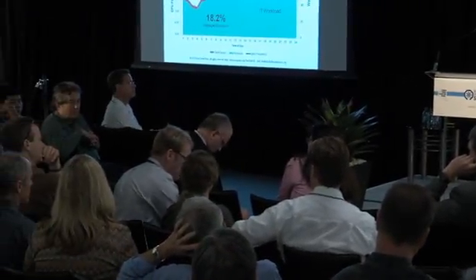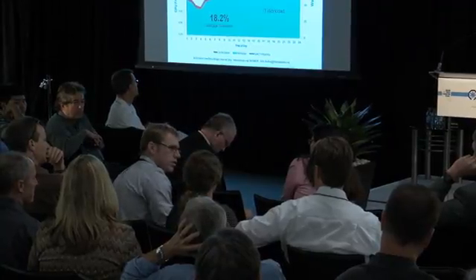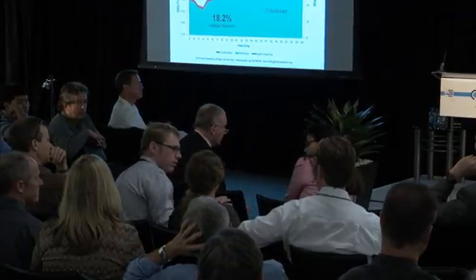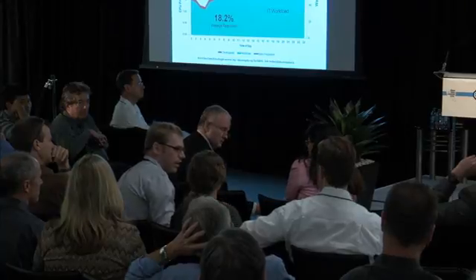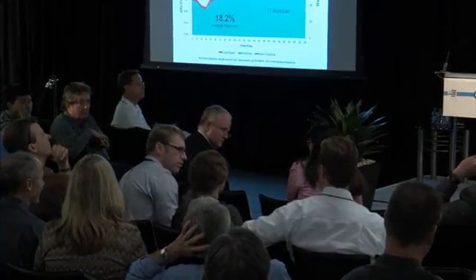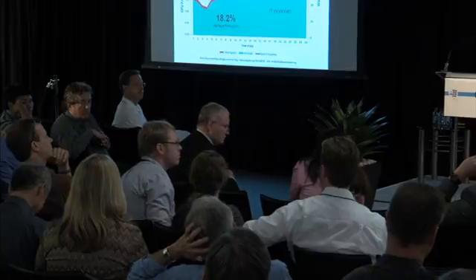Yeah, so we actually did a lot of playing with the server fans to eliminate it, because in certain instances we would run the CPU hotter, then notch up the server fans to see what would happen, and you'd see the leakage current decrease since we had all the server fans, so you could extrapolate it out. To be honest, about 75, 76 degrees Fahrenheit was kind of the happy medium from my testing.